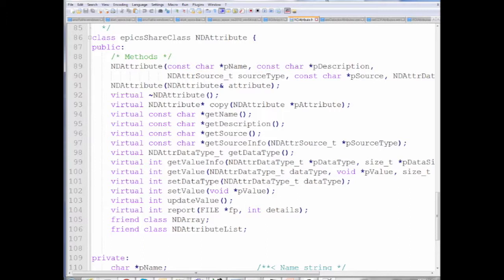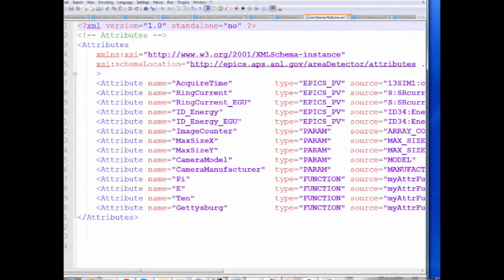You can have multiple NDStandardArrays plugins in your configuration — one making raw data into a waveform record, another for processed data, and your client just switches between them. You can even have three drivers and one standard arrays plugin so you have three cameras but only one can be viewed at a time — as done at the Australian Synchrotron — reducing system complexity because there's only one client looking at one thing.